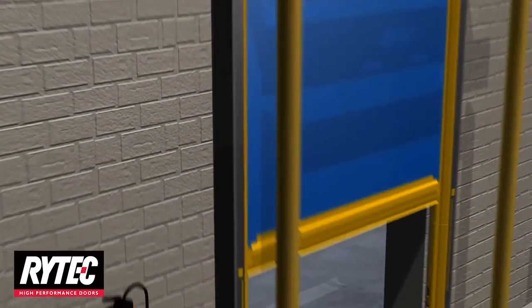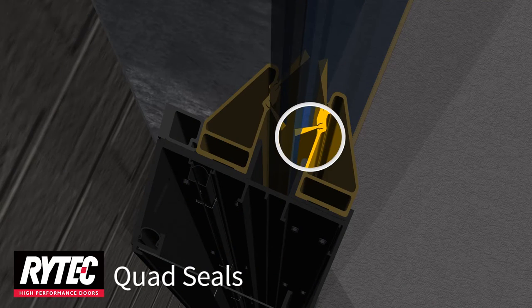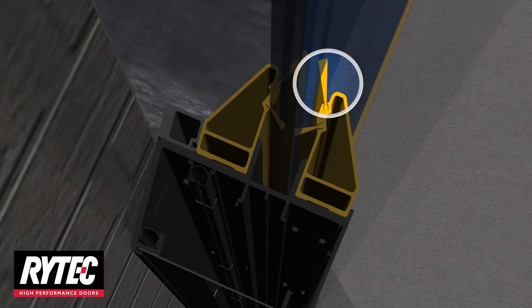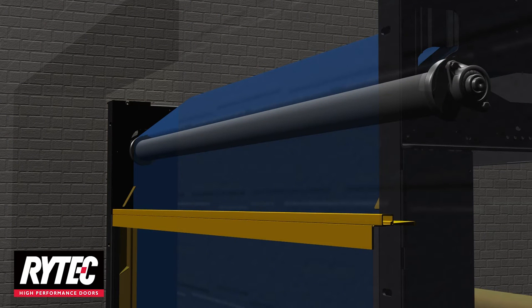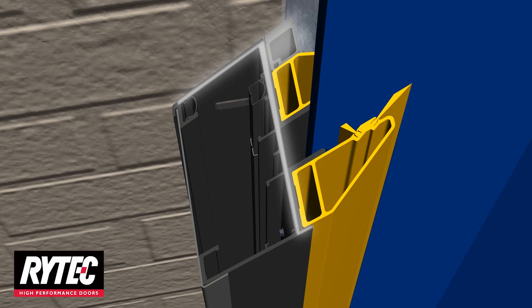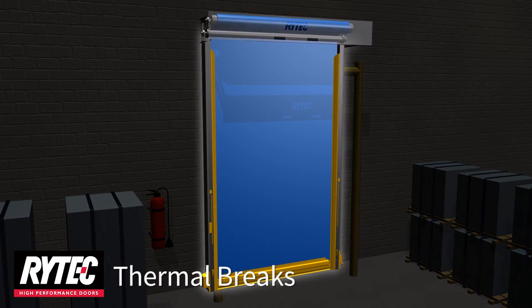The thermal envelope is completed with a full perimeter seal. Quad seals in the side columns seal the entire door panel in four places. The idler barrel and brush seals maintain a tight seal at the top of the opening, and insulated breakaway tabs and a flexible low-temperature, fully sealed bottom edge ensure the bottom of the opening is securely sealed at the floor. Thermal breaks are integrated into the door's construction to reduce the flow of thermal energy and help maintain environmental separation, located in the side frames, bottom bar, and head assembly for maximum efficiency.